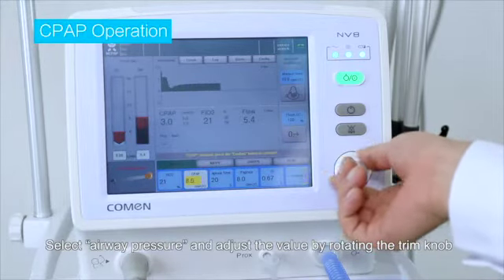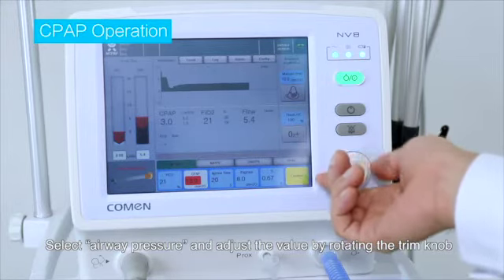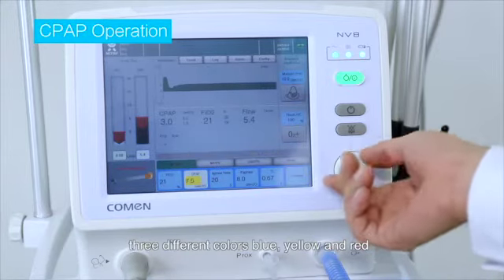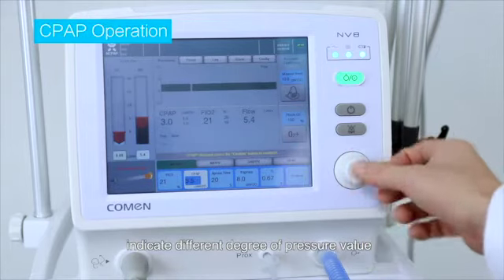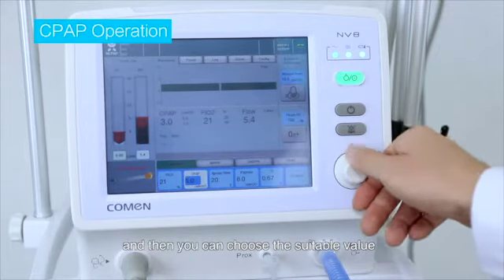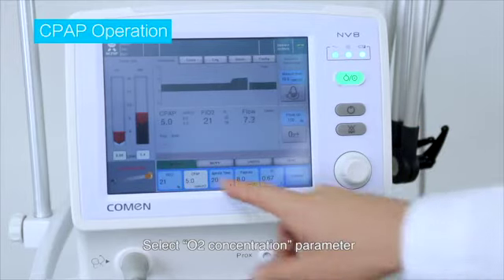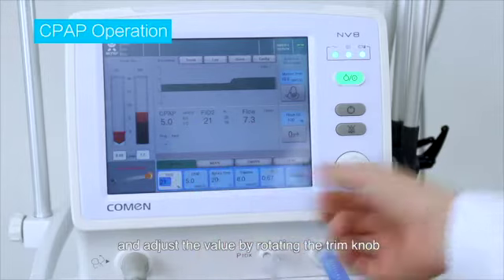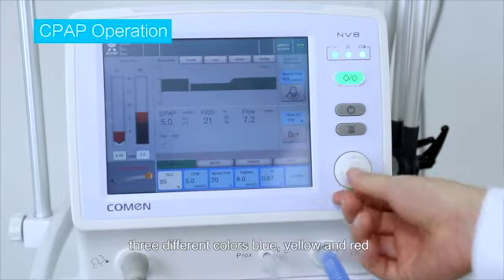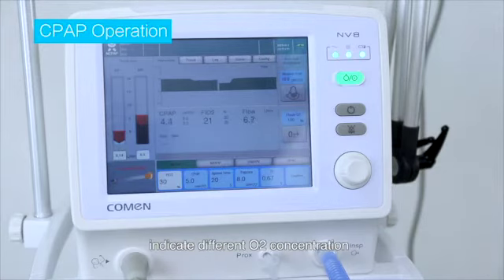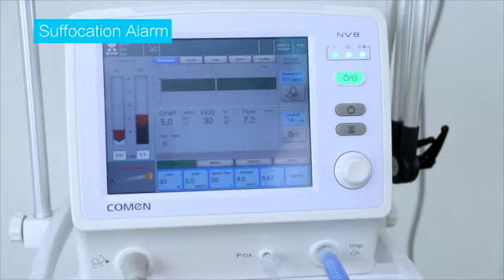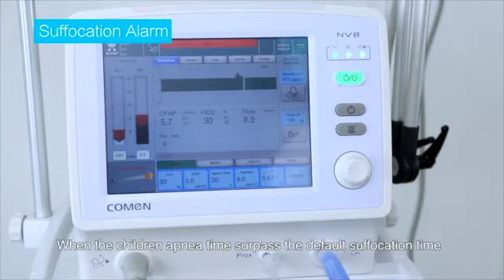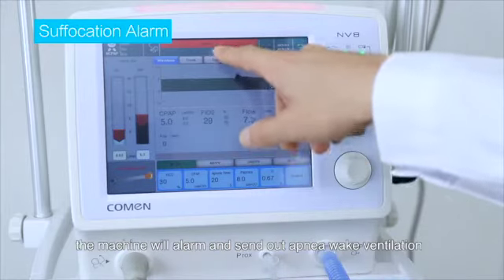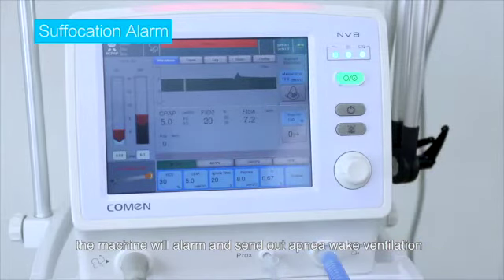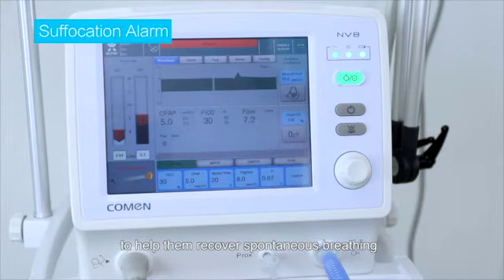Select airway pressure and adjust the value by rotating the trim knob. 3 different colors blue, yellow and red indicate different degree of pressure value, and then you can choose the suitable value. Select oxygen concentration parameter and adjust the value by rotating the trim knob. 3 different colors blue, yellow and red indicate different oxygen concentration, and then you can choose the suitable value. When the children apnea time surpass the default suffocation time, the machine will alarm and send out apnea-wake ventilation to help them recover spontaneous breathing.